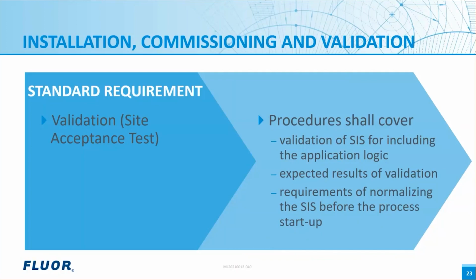It's vital that post-validation, the system is normalized. This includes removal of all the bypasses and forces, disabling of the forcing feature, and restoring the timers and counters to the design value. For field instrumentation, ensure that they are operational with all temporary arrangements for testing removed.